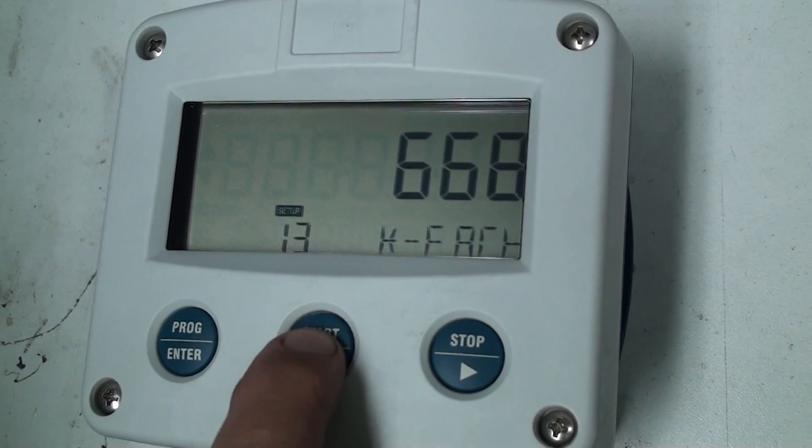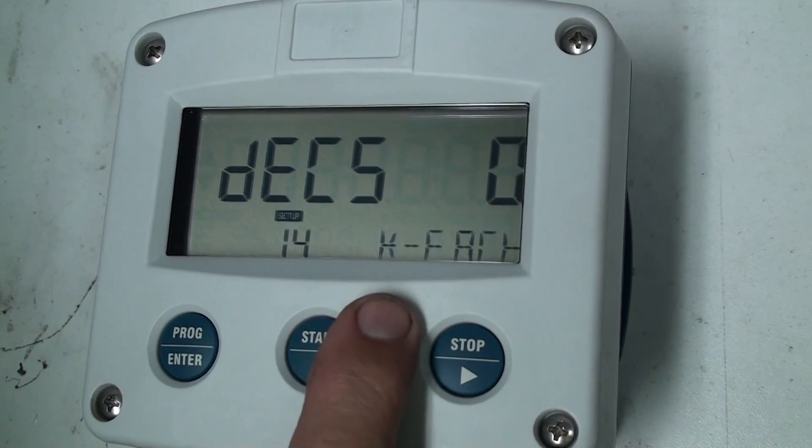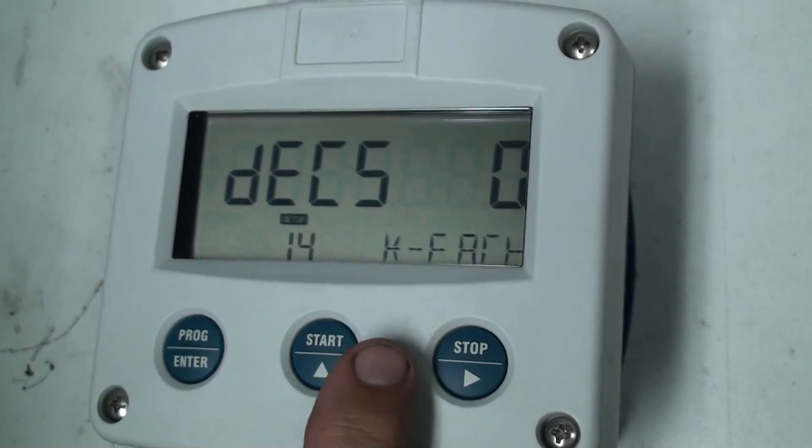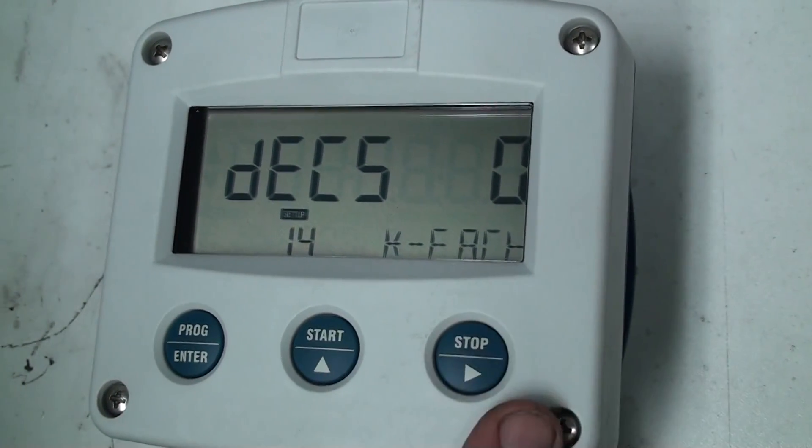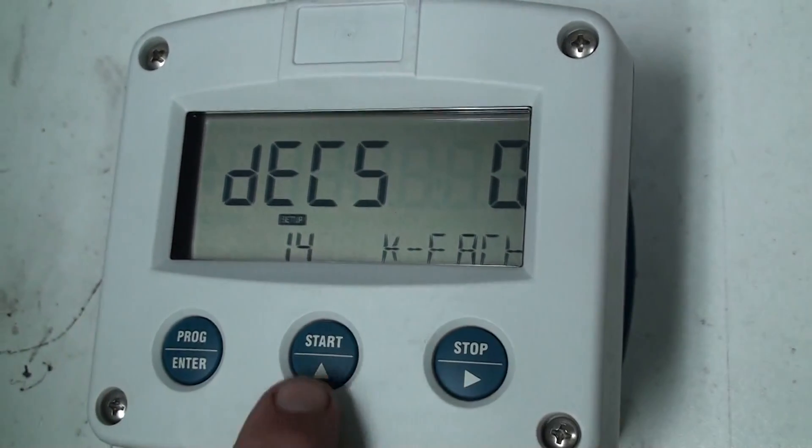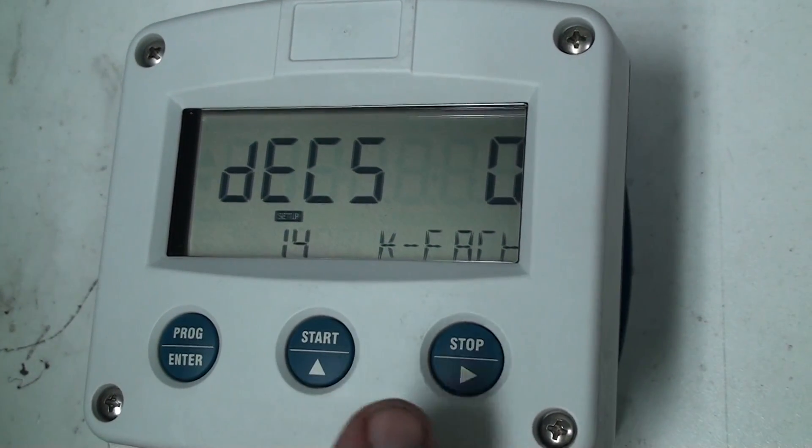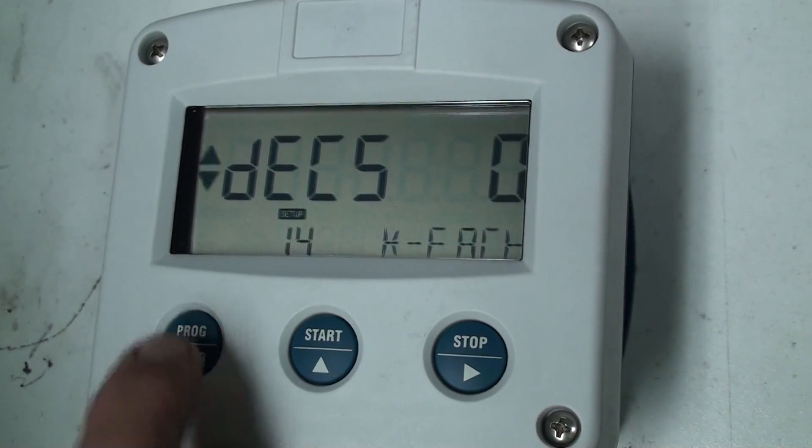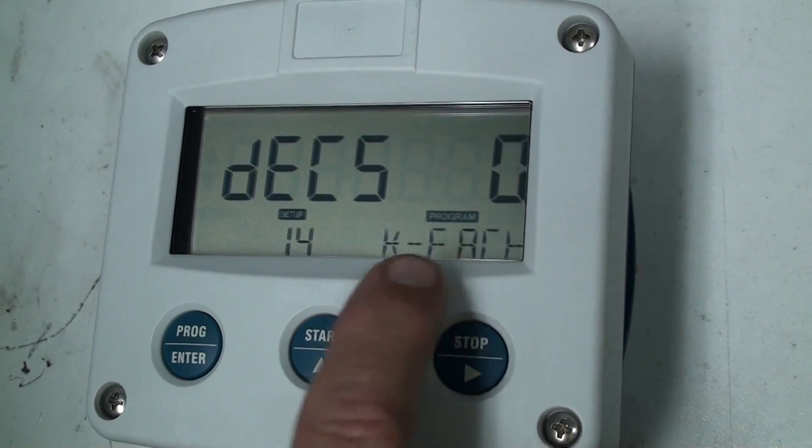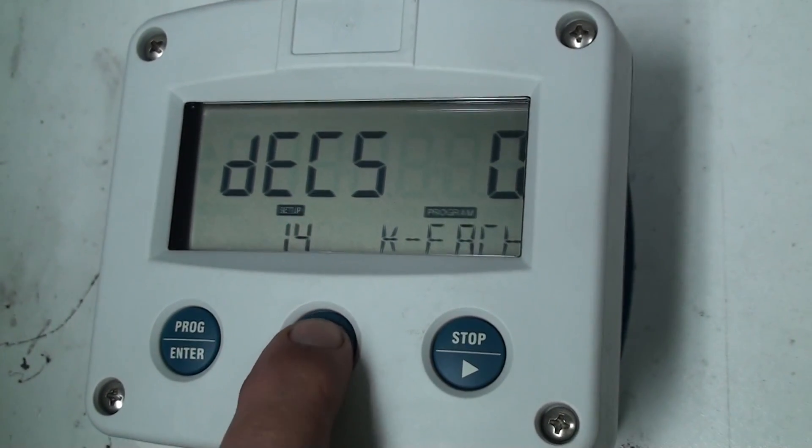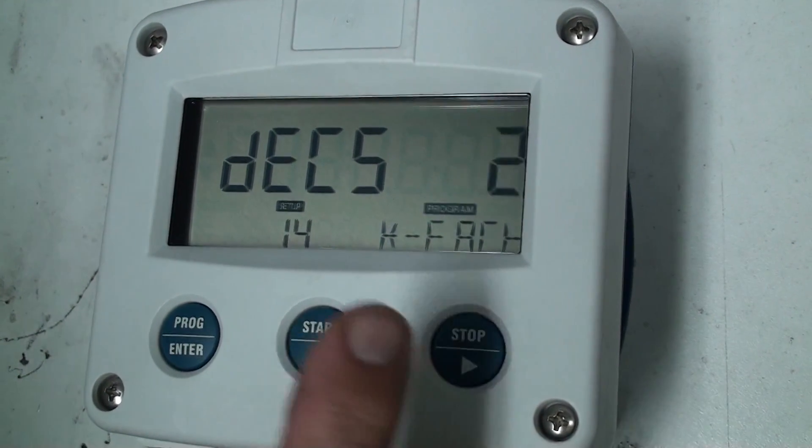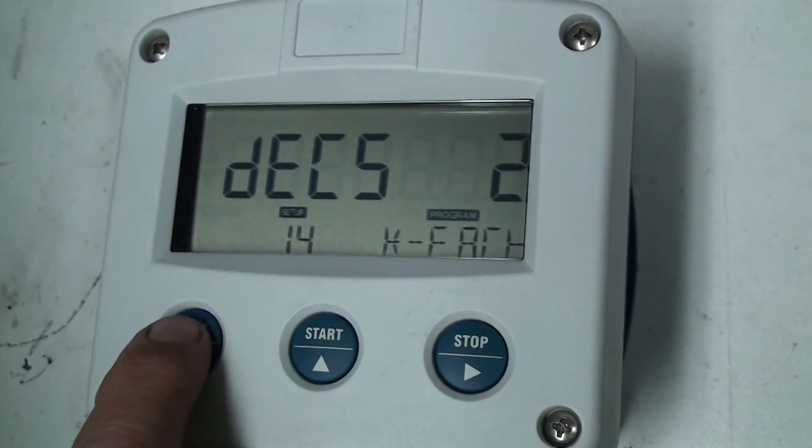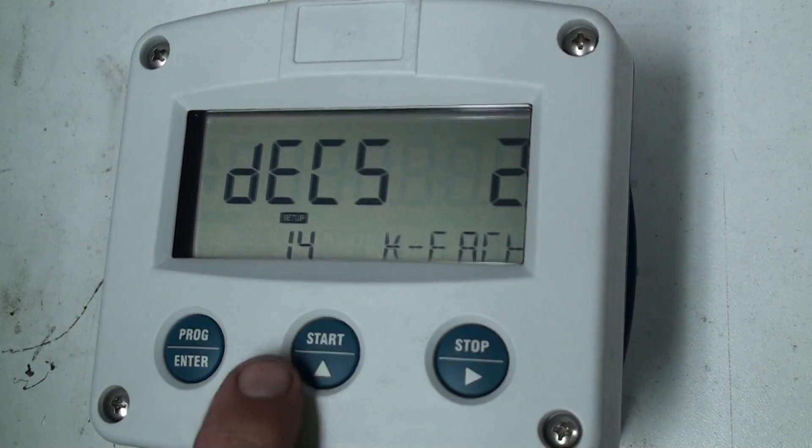Now chapter 1.4 is for the decimal points for the k factor. At the moment chapter 1.3 I've entered in 668 now I need to put two decimal points so that it will read 6.68. We do that by pressing the program key and you'll see this program flashes then I can change it to two decimal points and then I press enter and that has loaded that into chapter 1.4.